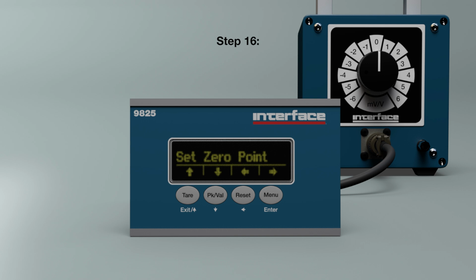Step 16. Press and hold the tare key for 2 to 3 seconds to exit the setup menu. The calibrated value will be displayed. An input of -4 millivolt per volt will display as -40,000 and an input of 4 millivolt per volt will display as 40,000. Calibration is now complete. In this example, we used a load simulator to perform the calibration. The same process can be followed to calibrate the instrument with a sensor using live weight, based on the output and capacity of the sensor.